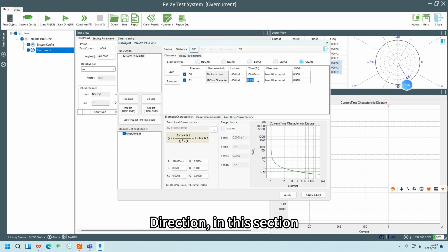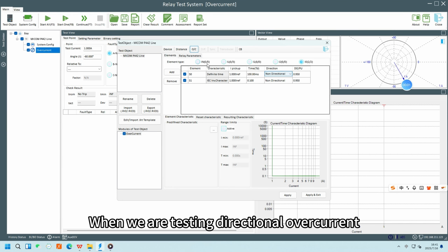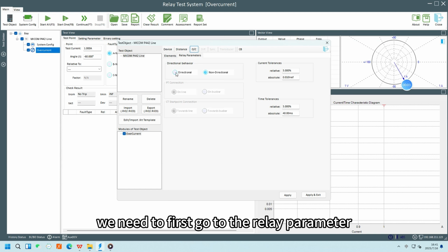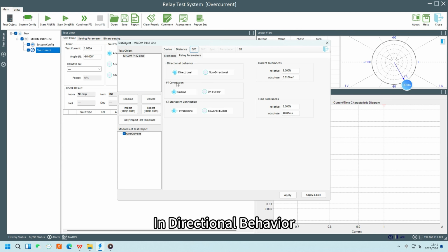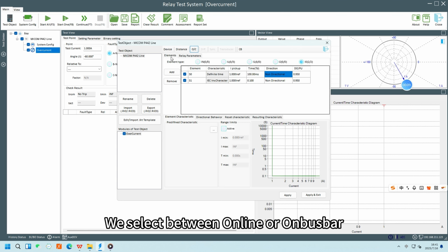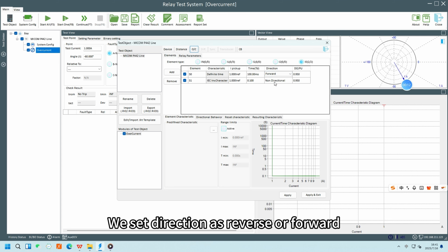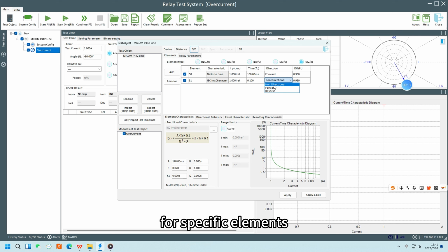Direction. In this section, we can configure the directional settings of the relay. When we are testing directional overcurrent, we need to first go to the relay parameter, in directional behavior, where we enable the directional, and then according to the actual PT-CT connecting method, we select between online or on busbar. And then we go back to element, and set direction as reverse or forward for specific elements.